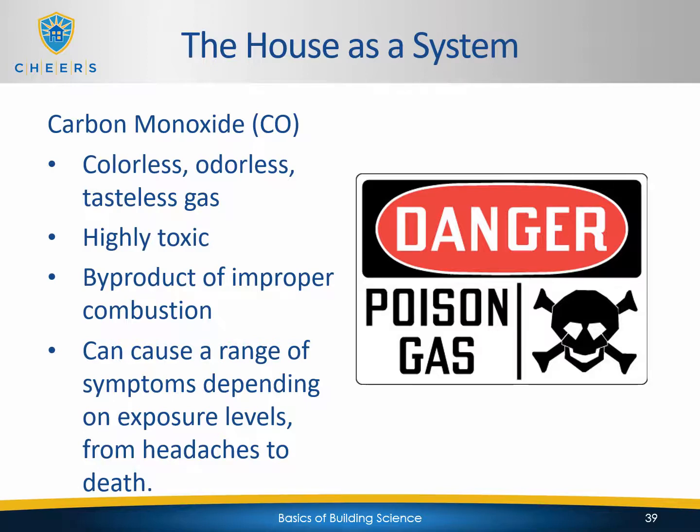So if the house is very airtight and there is nowhere for CO to draft out, or it's being drafted inside because mechanical ventilation is sucking it in from the appliance, they can cause very dangerous situations. If you read in the news or if you do research, you'll see that around the winter seasons, thousands of people die yearly from CO exposure. It's a very common thing to happen, and it's something that you definitely have to be aware of when performing modifications to the house.